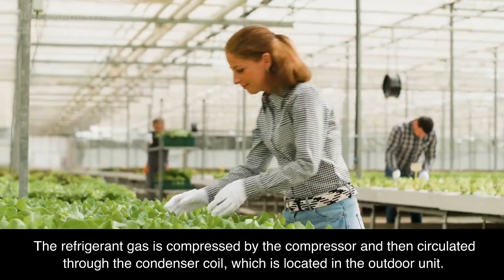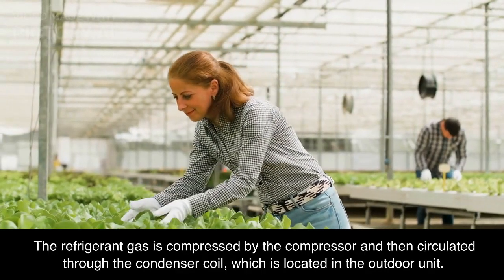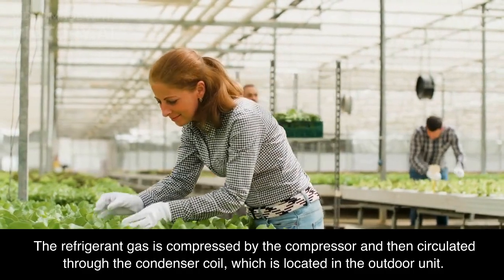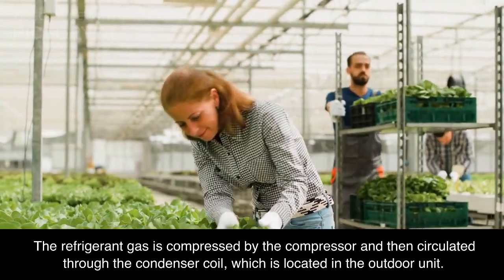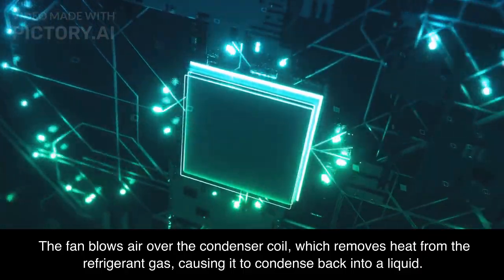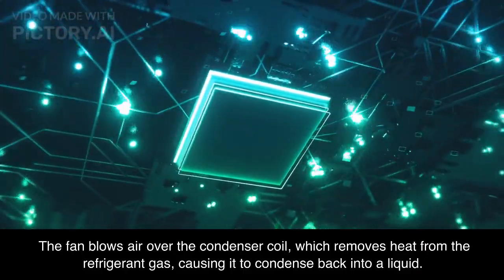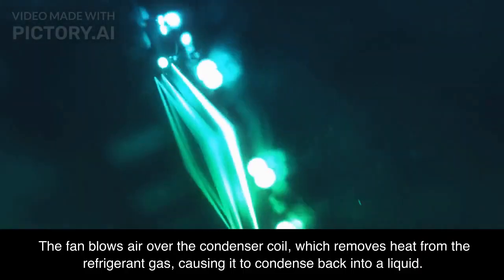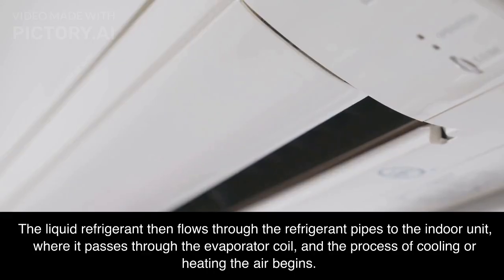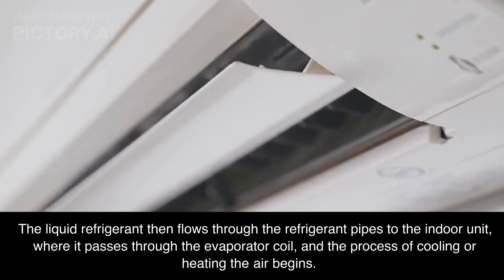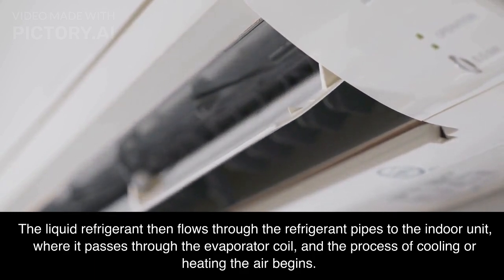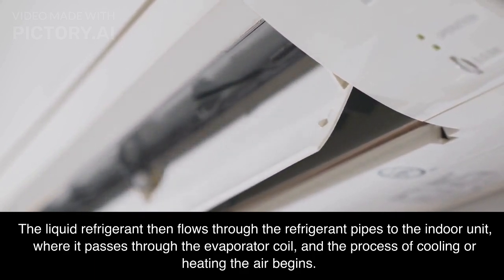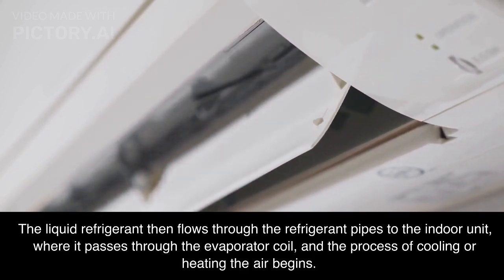The refrigerant gas is compressed by the compressor and then circulated through the condenser coil, which is located in the outdoor unit. The fan blows air over the condenser coil, which removes heat from the refrigerant gas, causing it to condense back into a liquid. The liquid refrigerant then flows through the refrigerant pipes to the indoor unit, where it passes through the evaporator coil, and the process of cooling or heating the air begins.